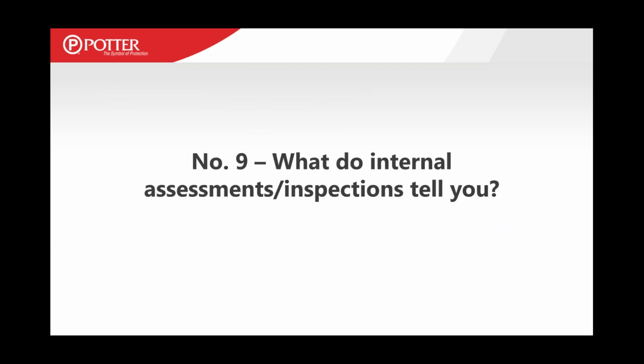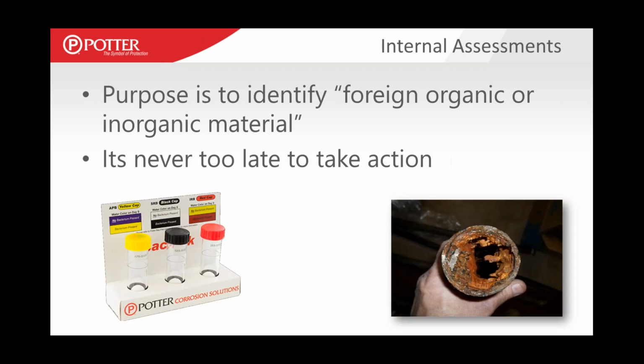So if we're doing these internal assessments, what are we looking for? What does an internal assessment or internal inspection tell us? Well, the purpose, directly out of Chapter 14, is to identify foreign, organic, or inorganic material. That's a mouthful, but that's the intent: to look for things inside the pipe that shouldn't be there, whether that's corrosion or a 2x4 or a glove left over from installation. We're assessing the internal condition of the pipe.